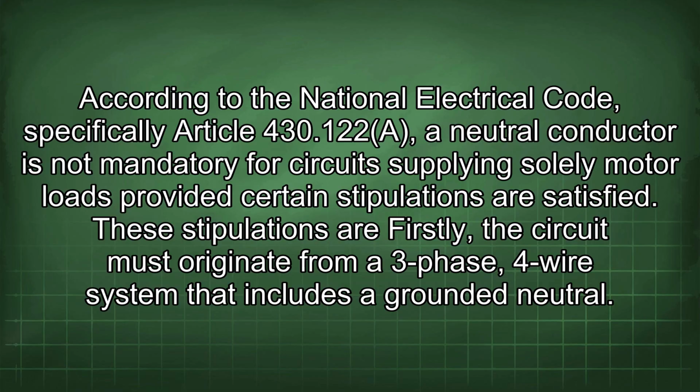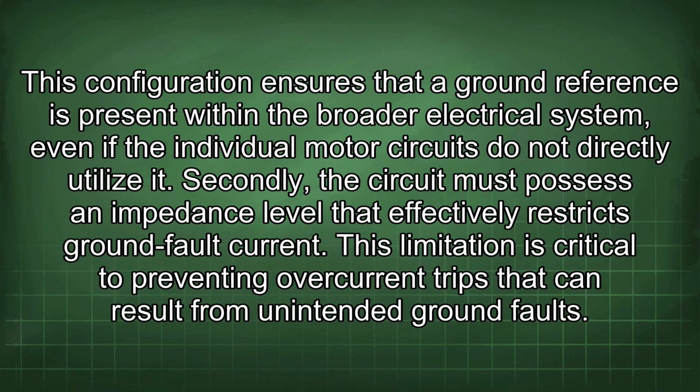These stipulations are: firstly, the circuit must originate from a three-phase, four-wire system that includes a grounded neutral. This configuration ensures that a ground reference is present within the broader electrical system, even if the individual motor circuits do not directly utilize it.